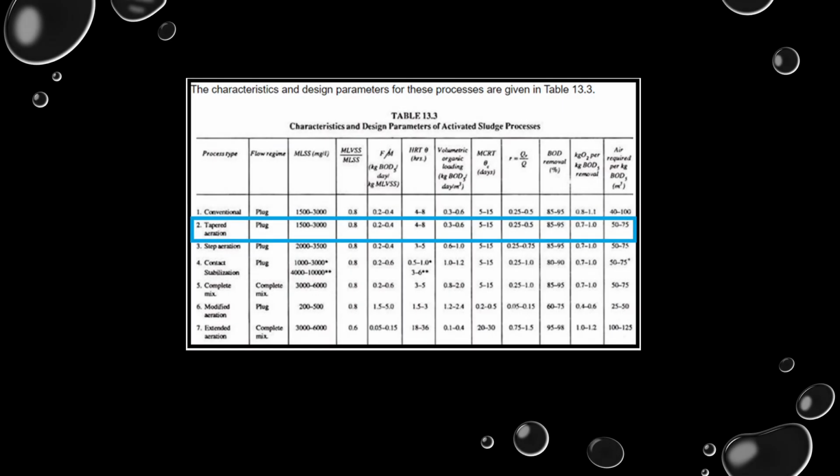Now, last, we have the tapered aeration design parameters. Okay, it is also a plug flow reactor. And also, the mixed liquor suspended solids is around 1,500 to 3,000 milligrams per liter.